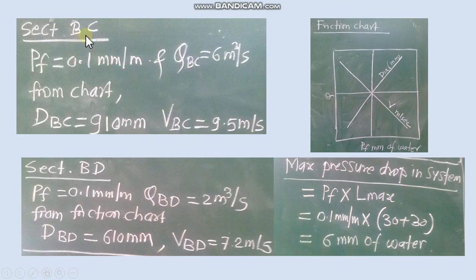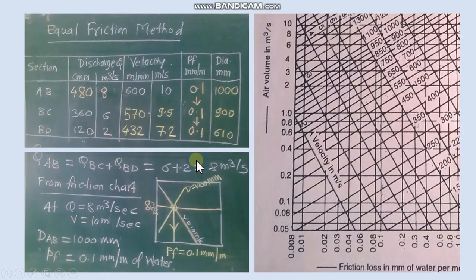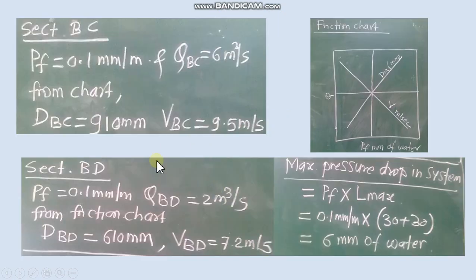Then for BC we know PF value that as per the method we write everywhere as the same. Now we have 0.1 and discharge in respect to duct. By using this we get for BC duct diameter and velocity. Similarly for section BD, PF value and respect to discharge from friction chart we get diameter and velocity.